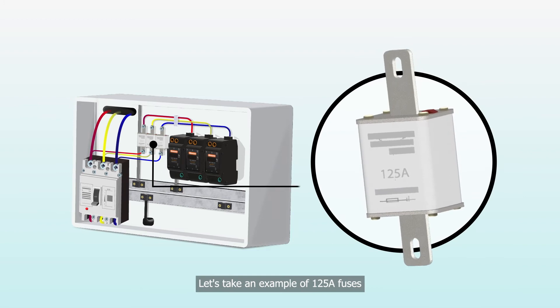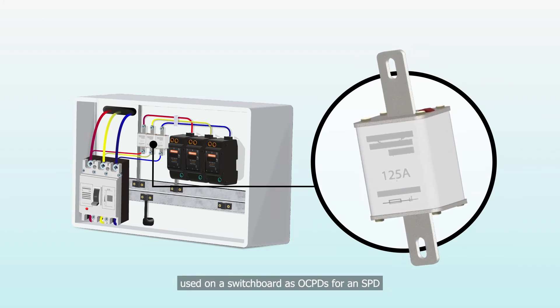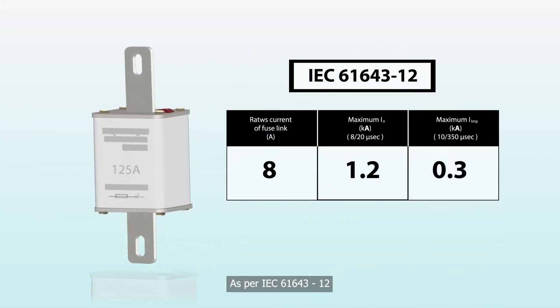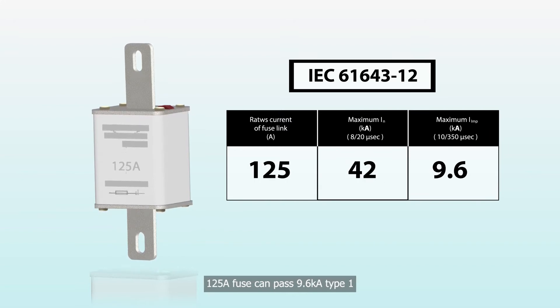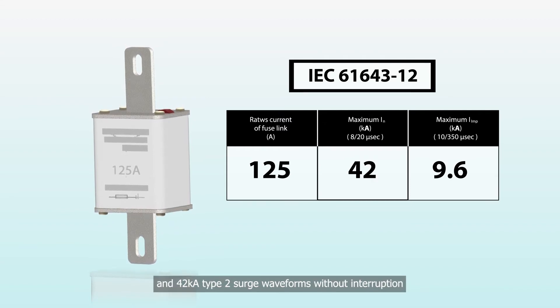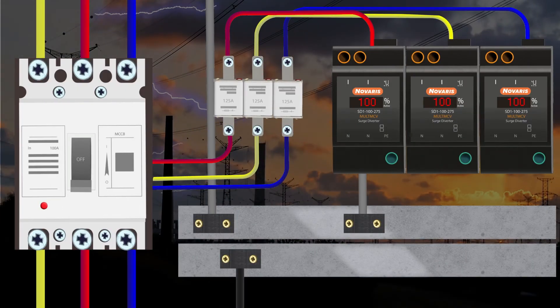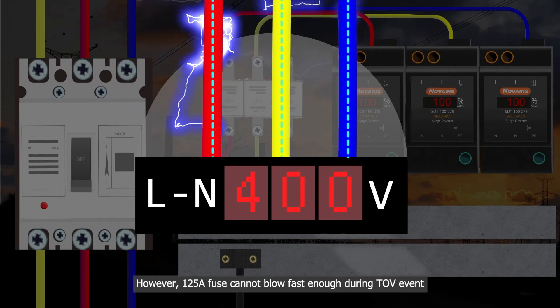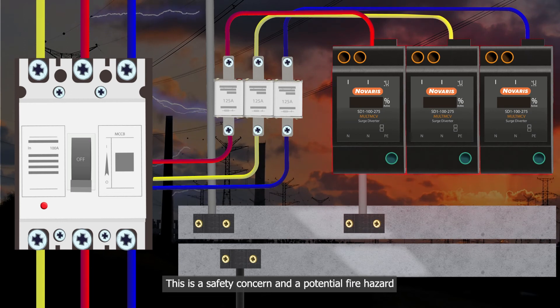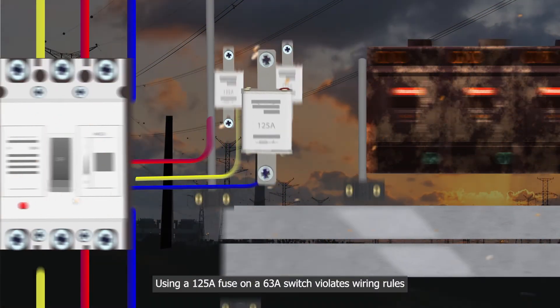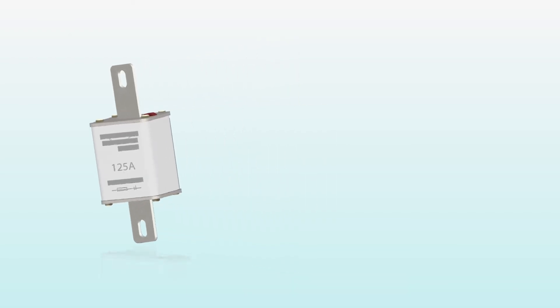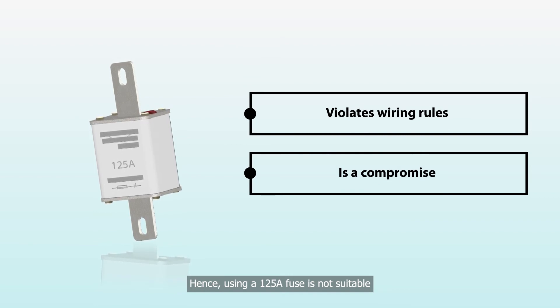Let's take an example of 125A fuses used on a switchboard as OCPDs for an SPD. As per IEC 61643-12, a 125A fuse can pass 9.6kA Type 1 and 42kA Type 2 surge waveforms without interruption. However, a 125A fuse cannot blow fast enough during a TOV event — this is a safety concern and a potential fire hazard. Using a 125A fuse on a 63A switch also violates wiring rules. Hence, using a 125A fuse is not suitable.